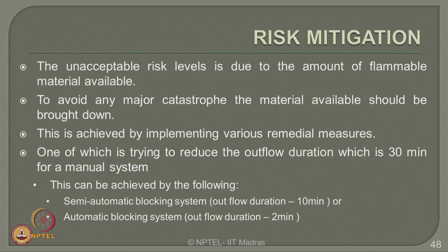Therefore, the recommendation to the given plant is to employ a semi-automatic blocking system to reduce the outflow duration from 30 minutes to 10 minutes, or employ an automatic blocking system which can further reduce the outflow duration from 10 minutes to 2 minutes. Dear friends, once the suppression system, either automatic or semi-automatic, is deployed in the plant, then the risk can be controlled, because the risk level is higher here since the suppression system is manual, which can result in 30 minute exposure of the outflow.